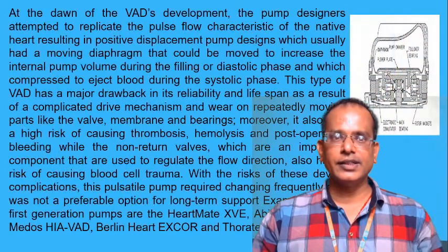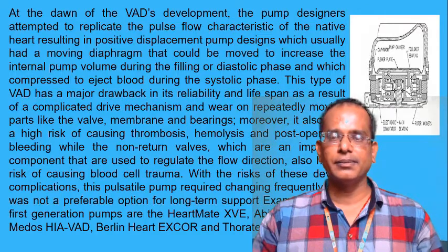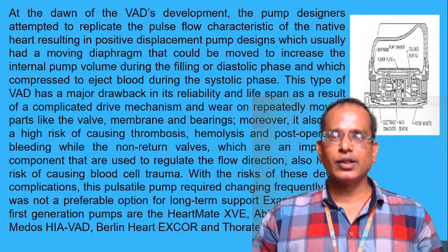In the first generation, at the dawn of VAD, pump designers attempted to recapitulate the pulsatile flow characteristics of the native heart, resulting in a positive displacement pump design, which usually had a moving diaphragm that could be moved to increase the internal pump volume during the filling or diastole phase, and which compresses to eject the blood during the systolic phase.